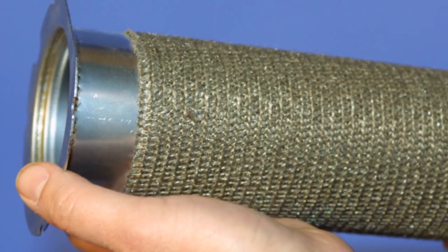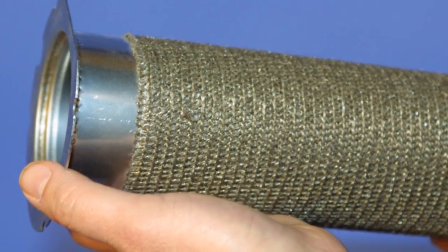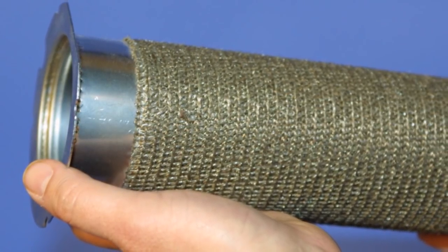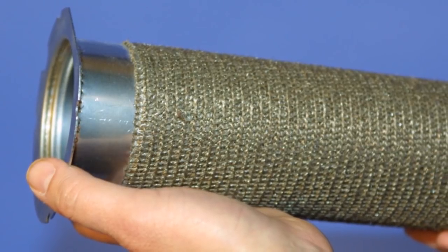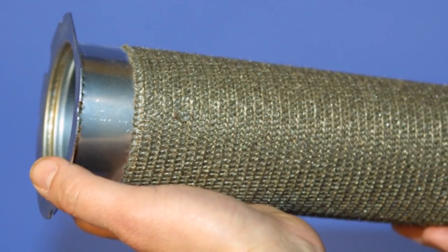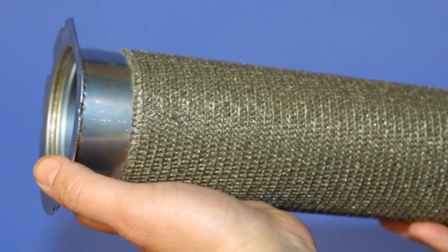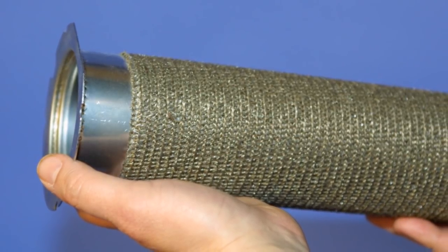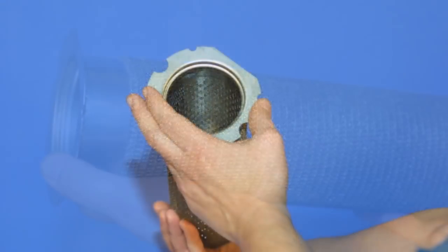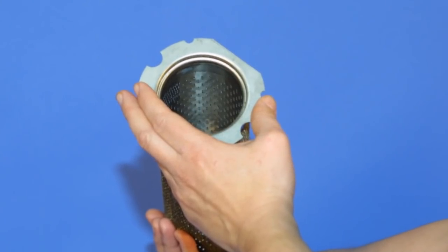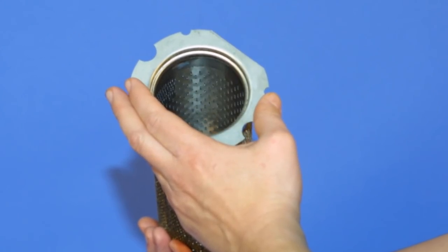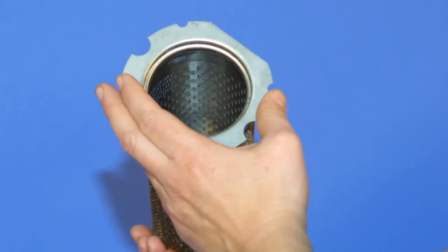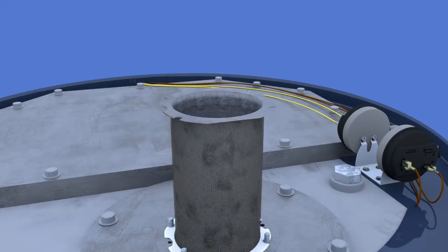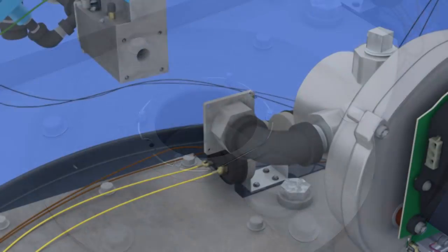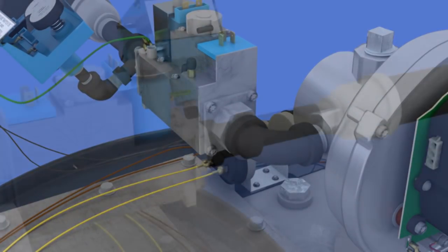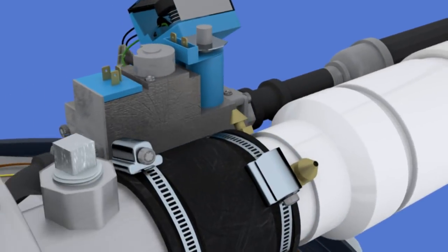The burner is comprised of a perforated stainless steel tube with a woven metal mesh wrapped around the outside. Do not attempt to stick objects into the woven metal for cleaning purposes, as this may damage the burner and reduce performance. If a blockage cannot easily be removed from inside the burner, compressed air may be used to blow out any buildup. The assembly can be reinstalled in reverse order. Reconnect power and gas and check for proper operation.